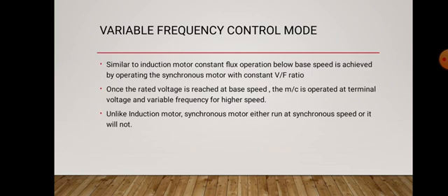So that is your variable frequency control mode. We have different types of controlling the frequency and speed of your synchronous motor. In the first case, we'll see about the variable frequency control mode. We have already seen in the induction motor drive the V by F ratio control, that is, by changing the frequency and the voltage in a constant ratio, we can change the speed of the induction motor. Similarly, here also, by varying the frequency, you are going to control the speed.